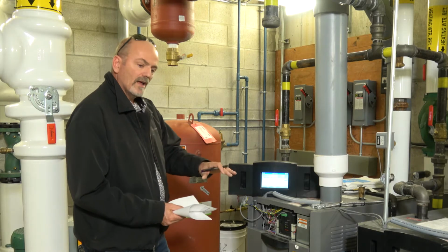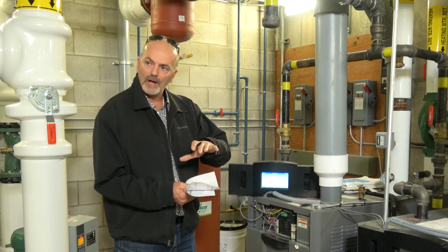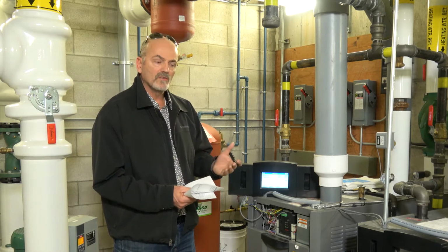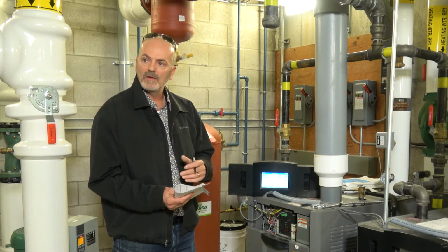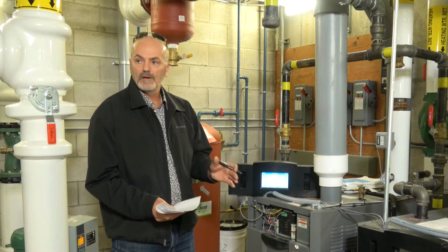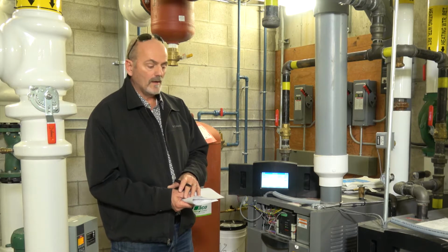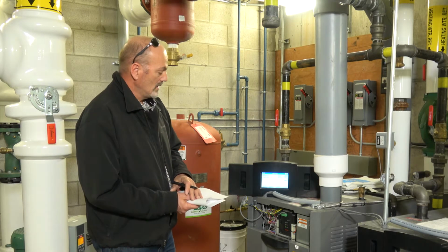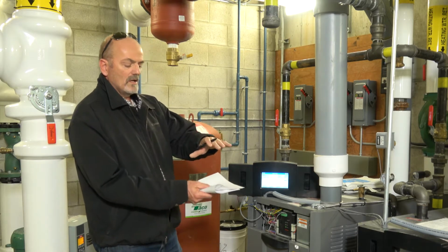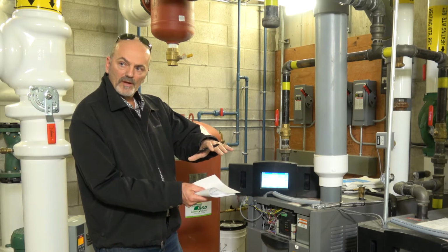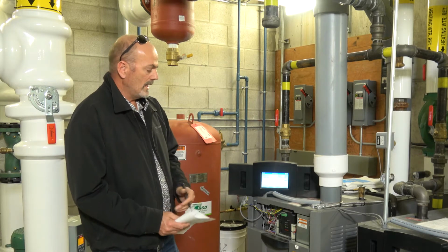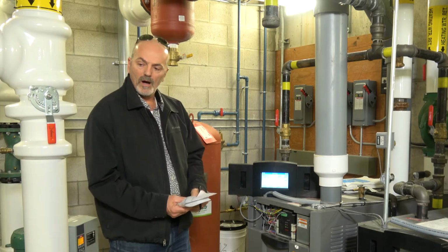And it will change that within a pre-programmed variance. Because it's fan coils, we don't want the water temperature getting too cold, so the air temperature doesn't get too cold. All right, coming off the fan coils, it will work between a lower and an upper temperature based on outside air temperature, and tell the boilers to fire and come on and go off.